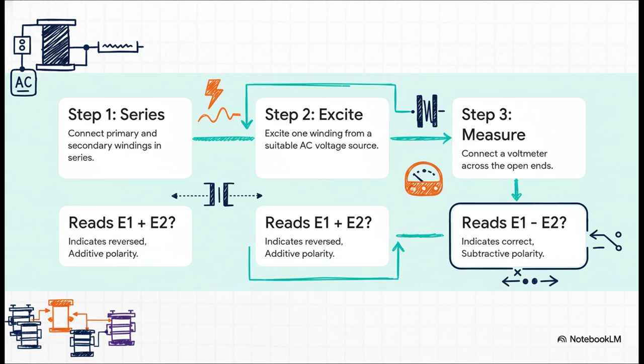If the voltmeter shows the difference between the two voltages, E1 minus E2, you've got subtractive polarity—everything's marked correctly and you're good to go. But if it shows the sum, E1 plus E2, that's a red flag: you have additive polarity and one of your labels is backwards. You have to fix that before anything else.